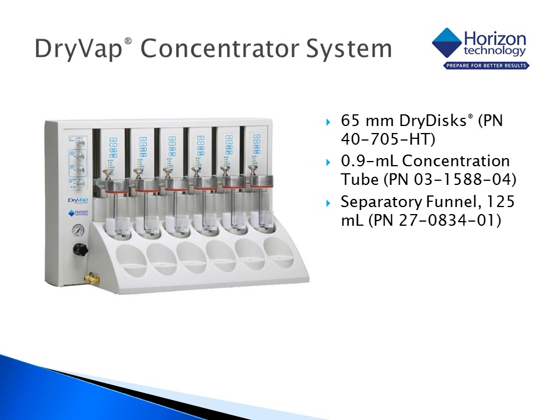The Horizon DryVap Concentrator was used for this work to dry and concentrate the samples. Its unique ability to dry samples online without the use of sodium sulfate minimizes losses associated with drying and concentration and maximizes recoveries of compounds of interest. The use of sodium sulfate to dry samples of residual water will often adversely affect recoveries. The DryVap uses a dry disc to remove residual water from the extracts via a hydrophobic membrane that allows solvent to pass through but not water.